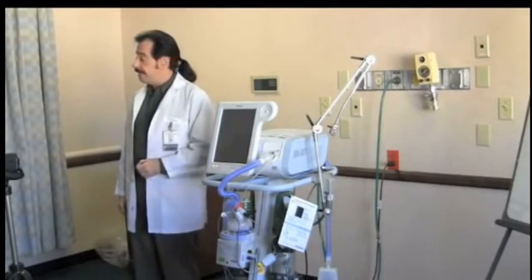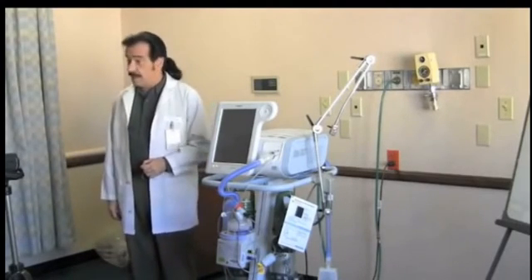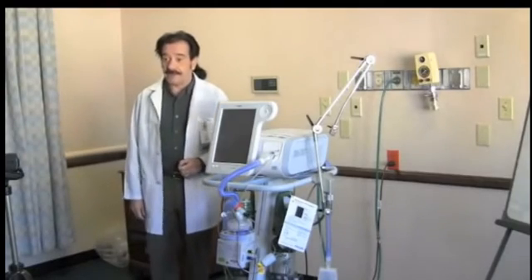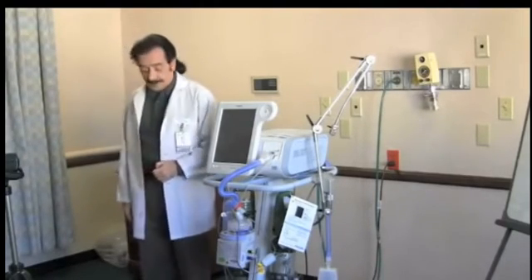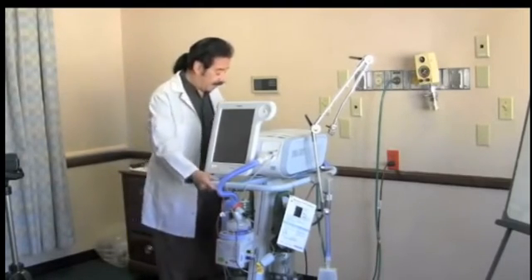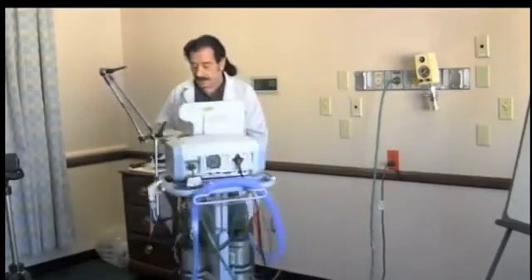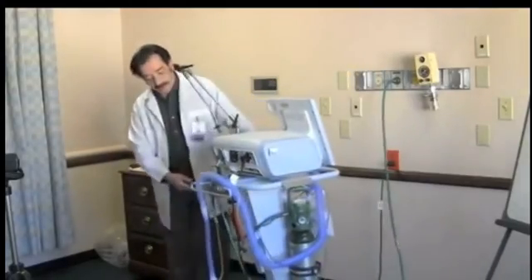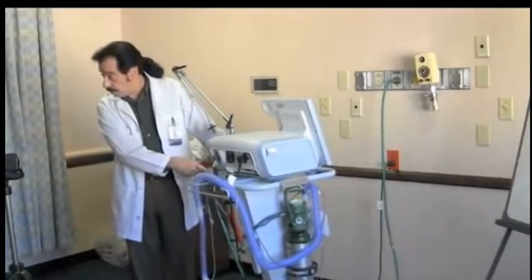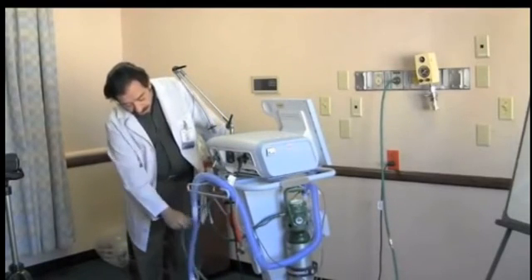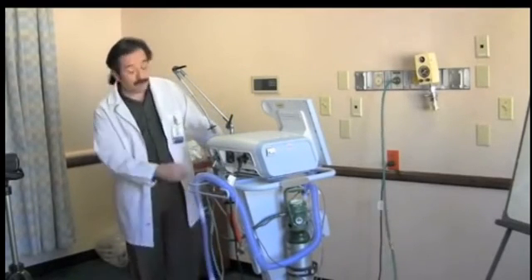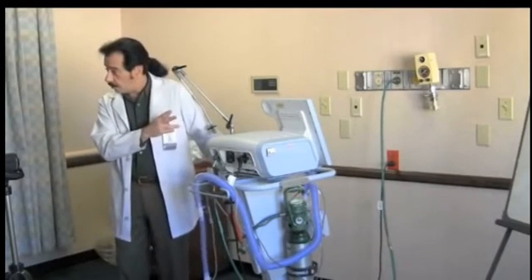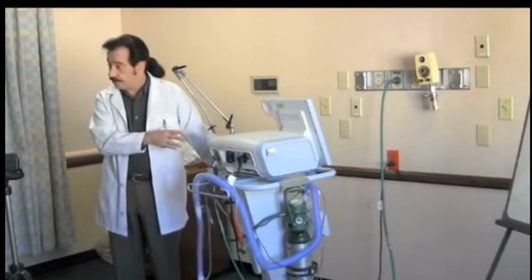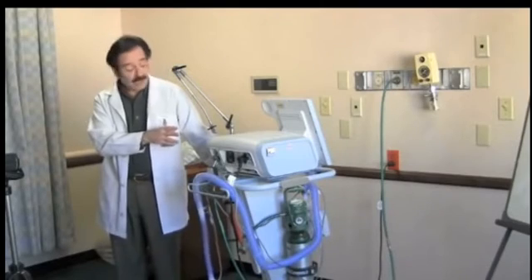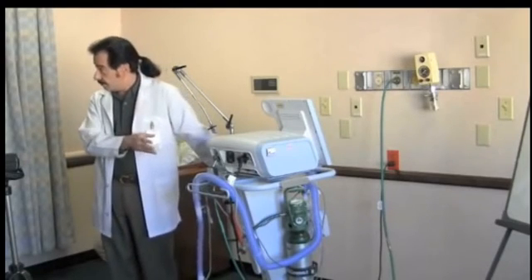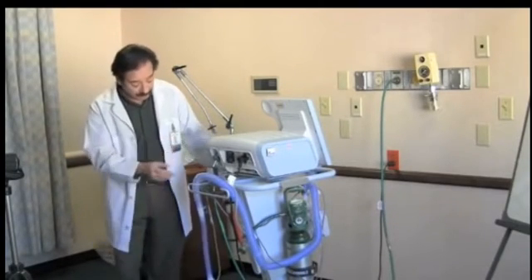Make sure that the machine is always plugged in, even when not in use, so that the battery can stay fully charged and conditioned. Okay? Now, in addition to the battery, it also includes the transport yoke. Okay? The center hose would hook up to your 50 psi source on the wall on oxygen. There's an internal turbine or blower that takes room air, so it mixes your FiO2 through a proportioning valve.